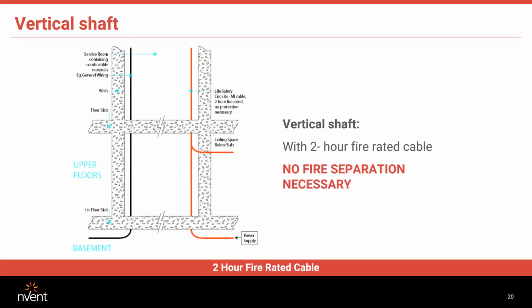If you have a vertical shaft with 2-hour fire-rated cable, no fire-rated separation is necessary. So for example, sometimes you're building a brand new building and you do have a dedicated shaft in the center that is 2-hour fire-rated. If you're going to run emergency feeders in that shaft, nothing alien to the emergency system can be in that shaft. If anything else alien to the emergency system is in that shaft, then you cannot use it as a fire-rated shaft. However, if you run MI cable in that shaft, you could run whatever else you want in that shaft because MI cable is a 2-hour fire rating in and of itself.